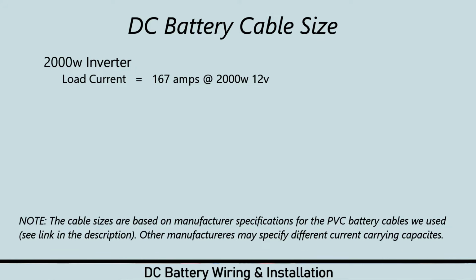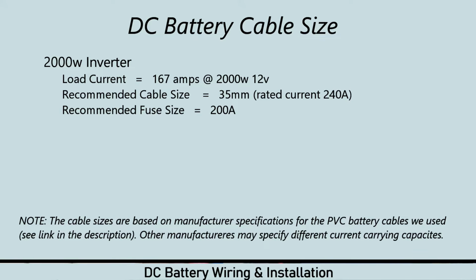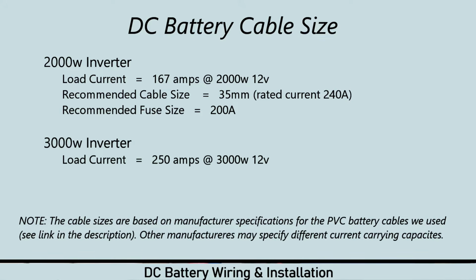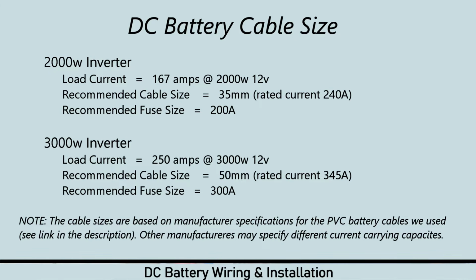So a 2000 watt inverter charger is going to pull 167 amps at 2000 watts. Now a 35mm cable is rated at 240 amps, so that's more than enough with a 200 amp fuse to protect the cable. The 3000 watt inverter charger is rated at 250 amps at 3000 watts. Now a 50mm cable is rated at 345 amps, so obviously that's more than 250 amps, and a 300 amp fuse, which is less than the cable, to protect the cable.